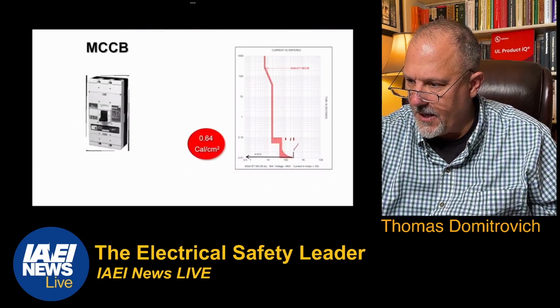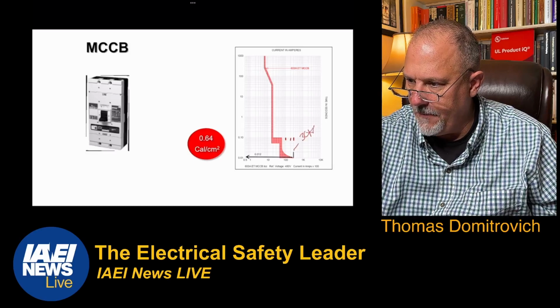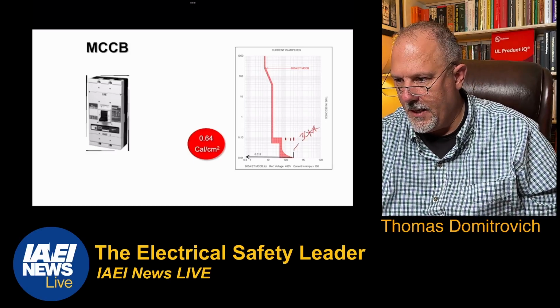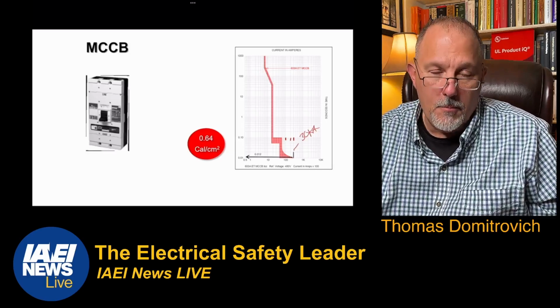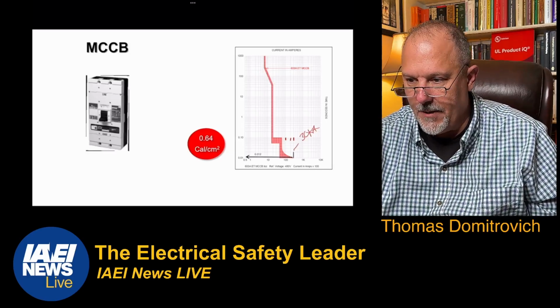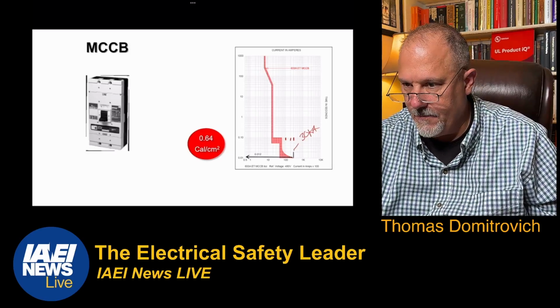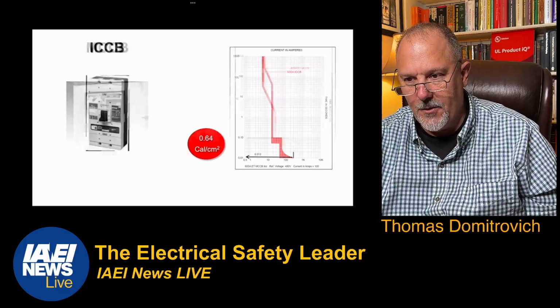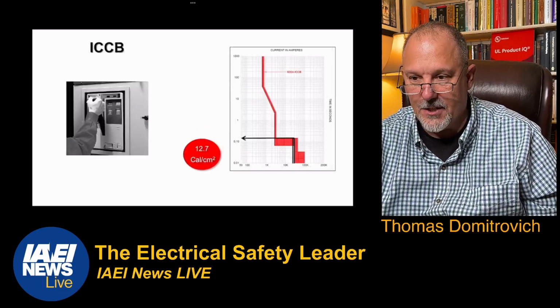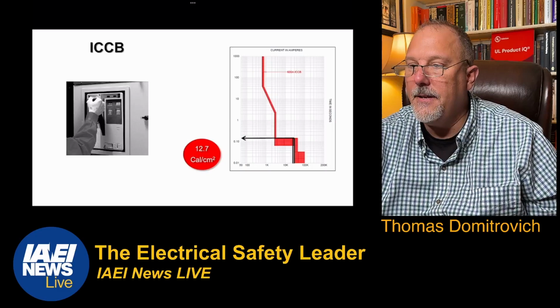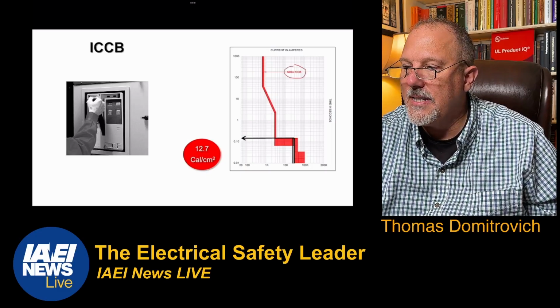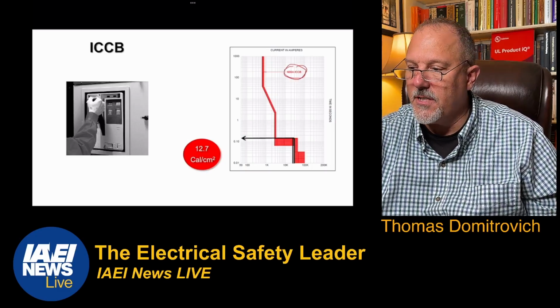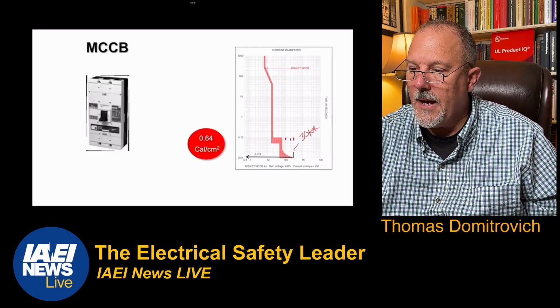So this is 30,000 amps, 30 kA. My clearing time is, if we just used 0.01 seconds, I'm at 0.64 calories. Now, I'm going to put in an insulated case circuit breaker. And again, it's still 600 amps. But you'll notice the difference between the curves. I had a short time delay.